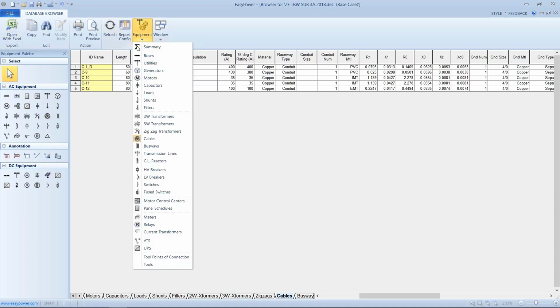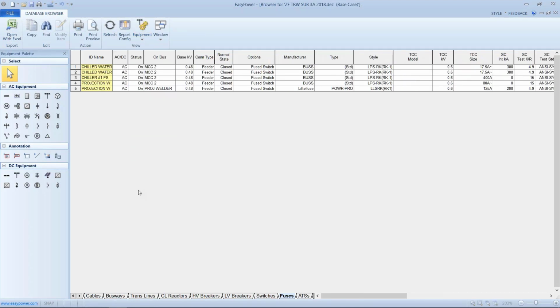And then the final element in this system is going to be the fuse switches. And as we look at the entry point, I can see over here that we have short circuit interrupt of 300,000 amps for a couple fuses, 200,000 for another, and then zeros. And ironically, these are the 2 fuses that were highlighted in red when we first started off.